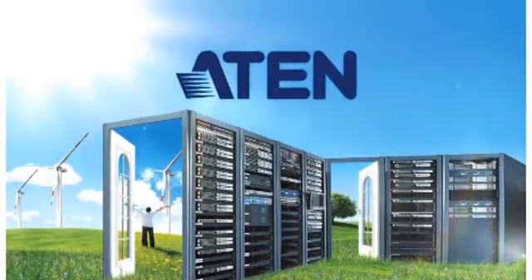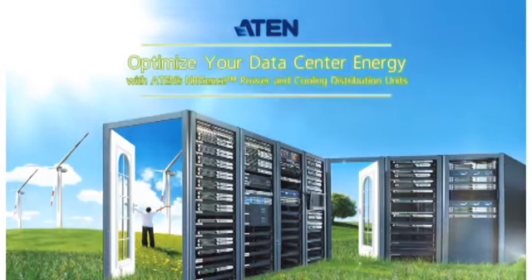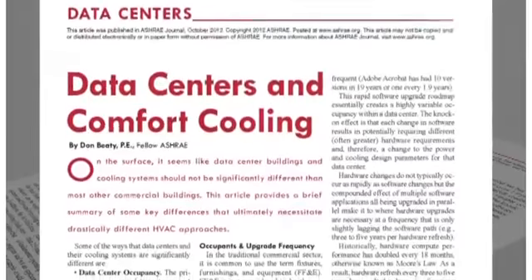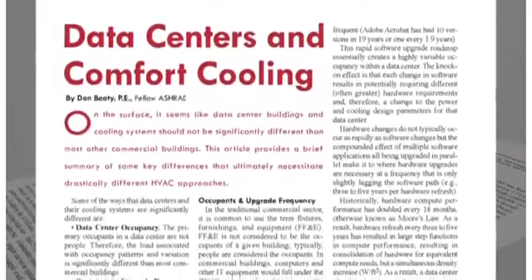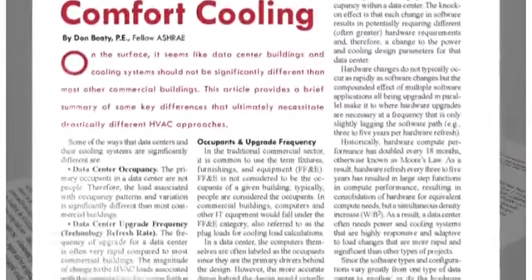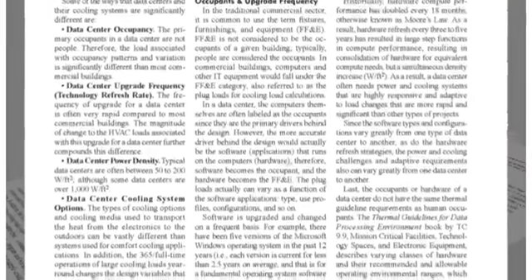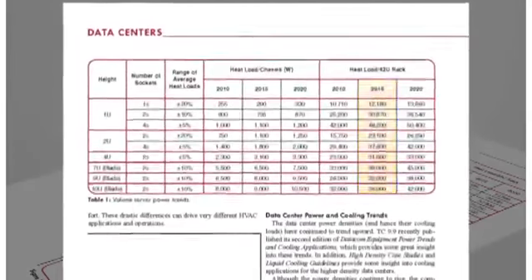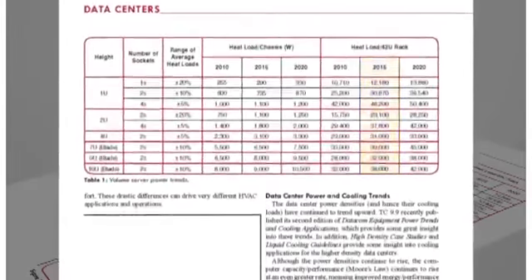Optimize your data center's energy with Aten's NRGence power and cooling distribution solutions. With rack density significantly increasing, power and cooling systems play a more critical role in data centers. According to ASHRAE's October 2012 article, Data Centers and Comfort Cooling, in the near future, the average power density of a 42U server rack will easily exceed 20 kilowatts per rack.